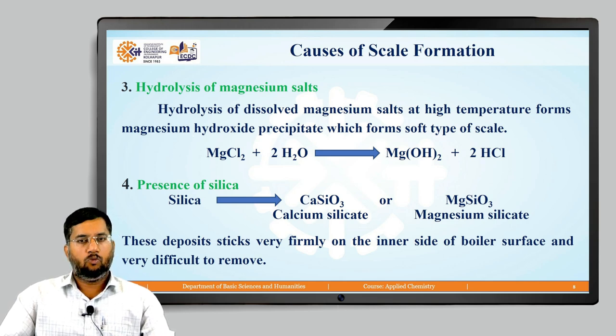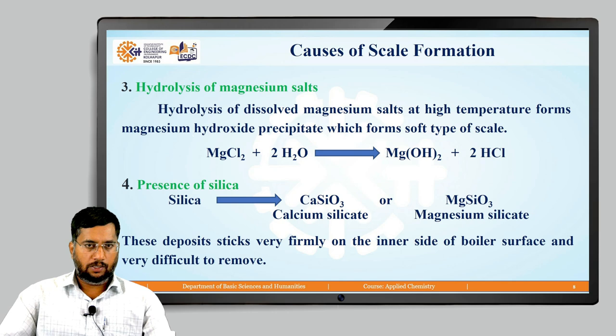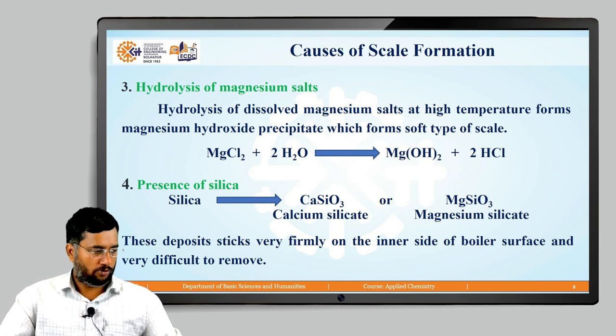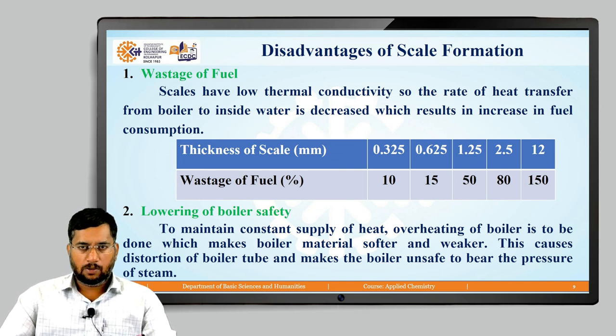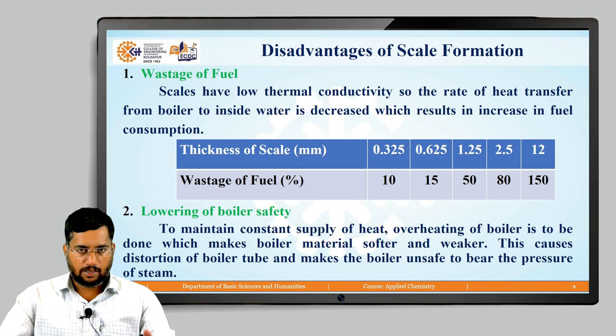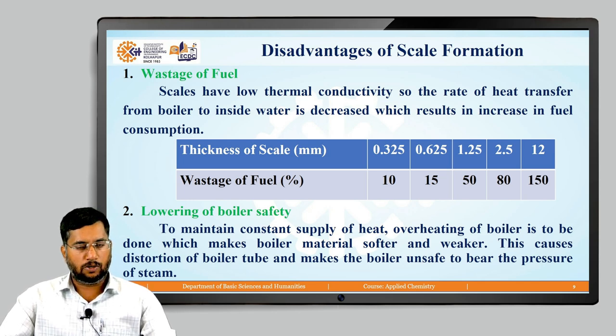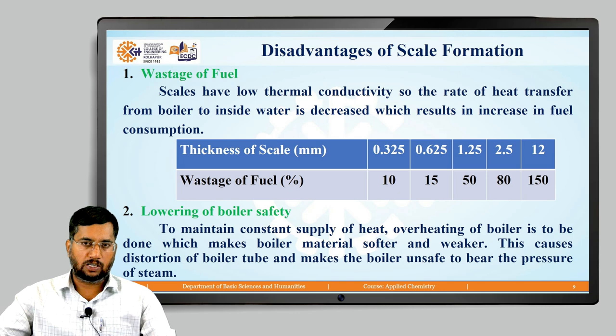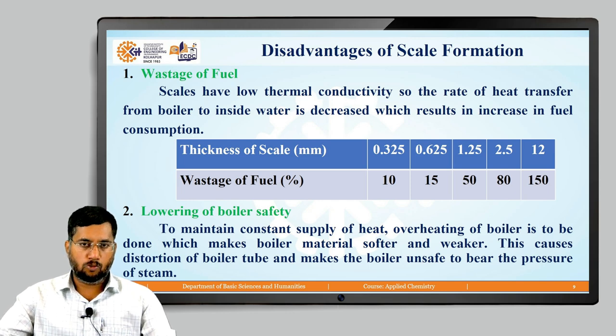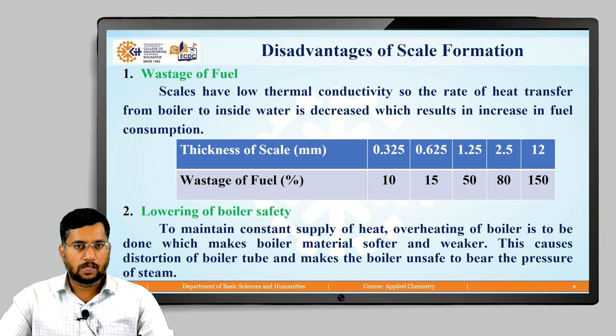This means that before feeding water to the boiler, pretreatment is required to remove dissolved impurities and avoid scale formation. Scale, like sludge, is a poor conductor of heat with low thermal conductivity. The rate of heat transfer from the boiler to the water decreases, resulting in increased fuel consumption. Extra heat must be provided to maintain the steaming rate, and whatever heat is applied does not pass efficiently through the scale to the water, leading to wastage of fuel.